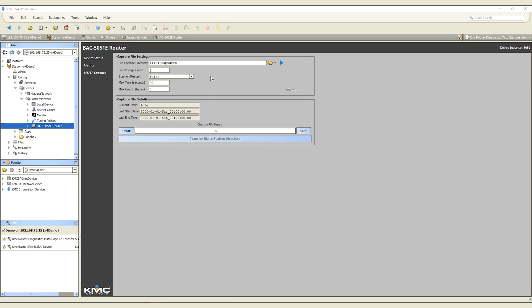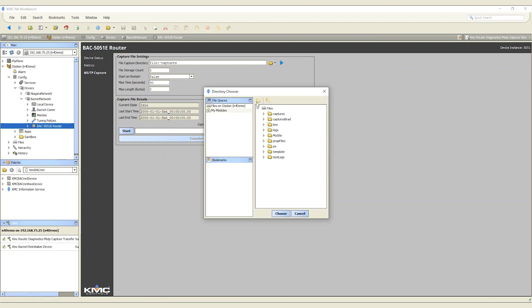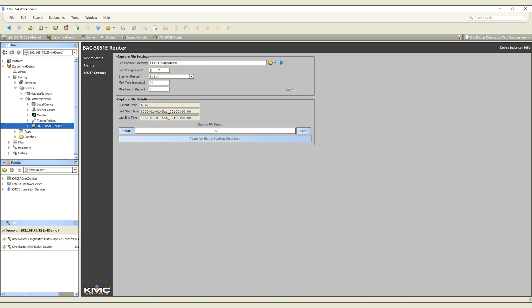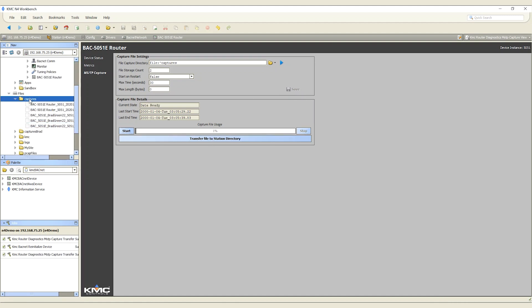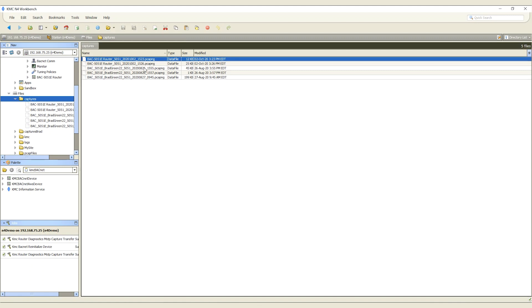Performing network captures is simple. First, select the MSTP capture view on the router object in your station. Then define where your captures will be stored, as well as the number of files to be held. When using a JACE, be mindful of the storage capacity when setting the number of files to be held. Next, set up your required capture details and start the capture. Once the capture is complete, transfer it to the station directory where it will be stored as a standard PCAP file.